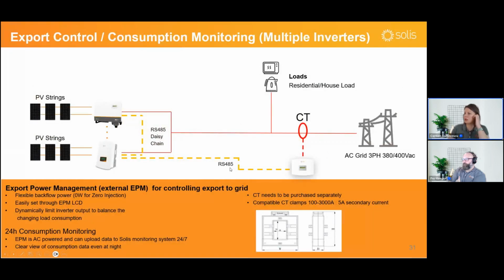This is what the setup looks like. The inverters are connected through RS485 in a daisy chain and can connect to the EPM. The EPM can sit at a far distance from the inverters, where the grid connection point is. This is very important, the location where this EPM is installed. In this case, it has to be here at the grid connection point. It needs CT clamps to measure the current on each of the phases.